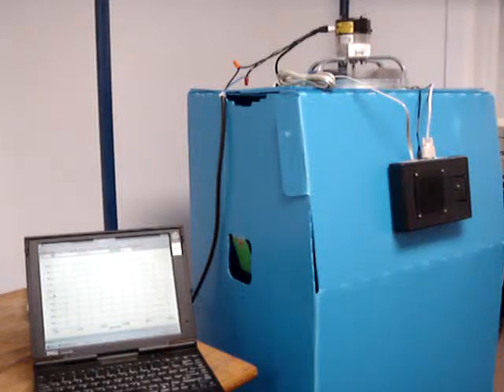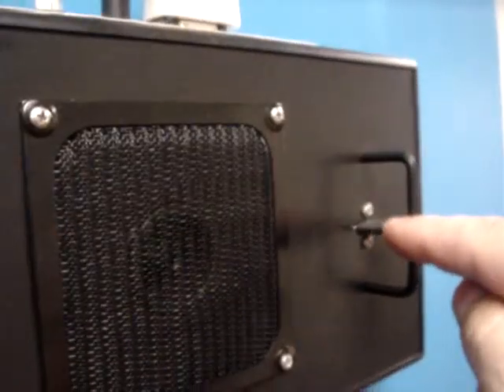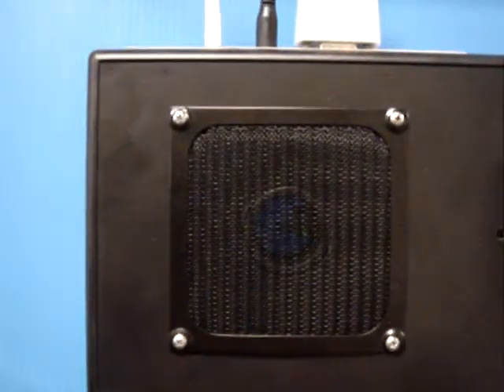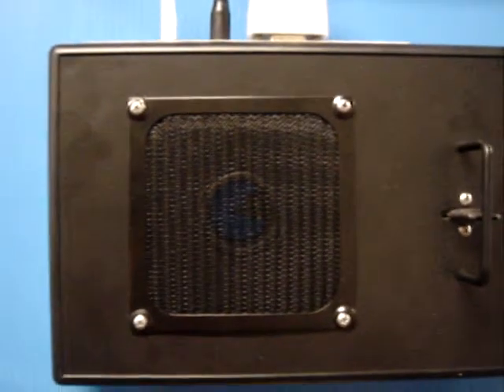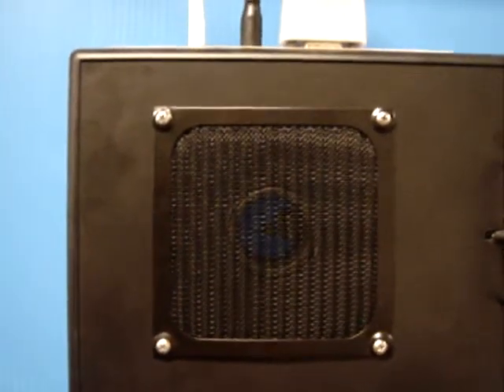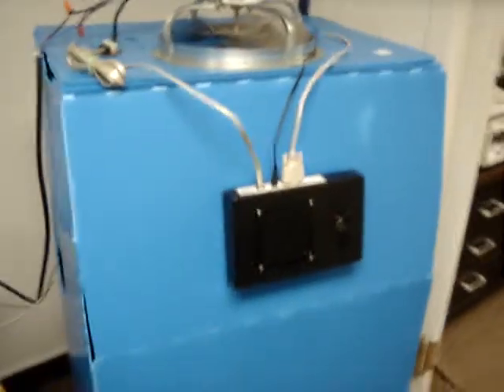And it's now, the CFM sensor is now detecting the airflow through an orifice. The CFM sensor has temperature sensors both outside and another one inside the server rack, and there's an orifice that it uses to sense the air, either the hot pressurized air being blown through the orifice to the outside, or the cold outside ambient air being sucked in through that orifice, and that's how it knows what to do with the exhaust fan.